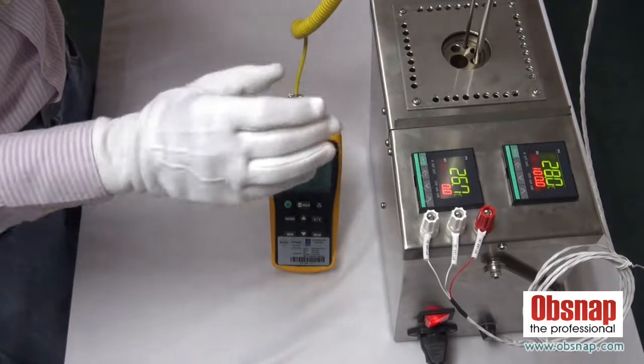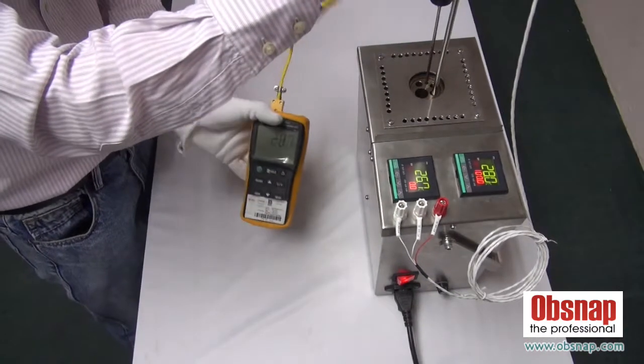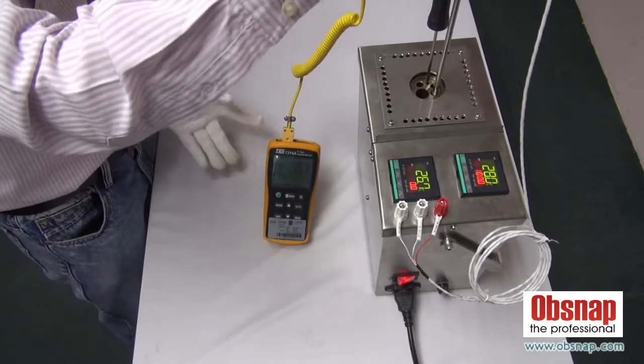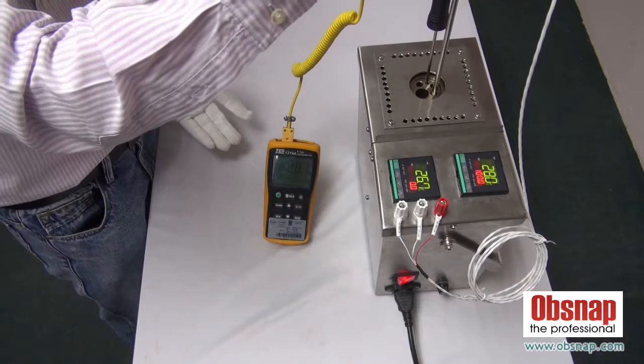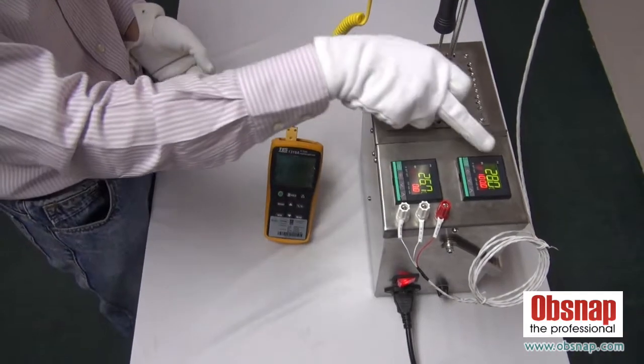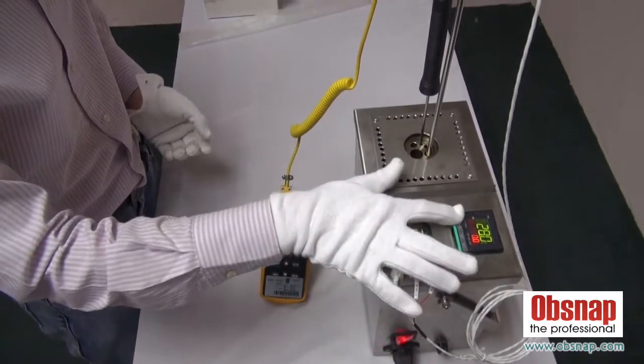That's why the dry box cannot be a reference to the thermocouple or any sensor. That's why we need to use another external higher reference sensor to be a reference during we are taking reading. We cannot directly take the reading at the setting on the dry box.